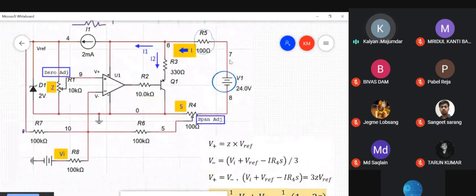এখানে দেখো এই পাওয়ার সাপ্লাই থেকে এসে এই রেজিস্ট্যান্সের মধ্যে দিয়ে this current is flowing, then it is flowing into this entire circuit. This is my box, so-called 2-wire transmitter, and this resistance is a part of that box. এখানে of course আমি assume করছি এখান দিয়ে যে কারেন্ট ব্রাঞ্চিংটা হবে, this is 100 ohm, this is 100k. So this current flowing into this wiper, that can be neglected with respect to the main current. 100 ohms or 100k বুঝতে পারছো is 1000 times different. If you neglect that 0.1% error, তাহলে এখানে ধরে নিতে পারছি this entire current is also the current flowing through R4. So current flowing through R4 is this loop current I.